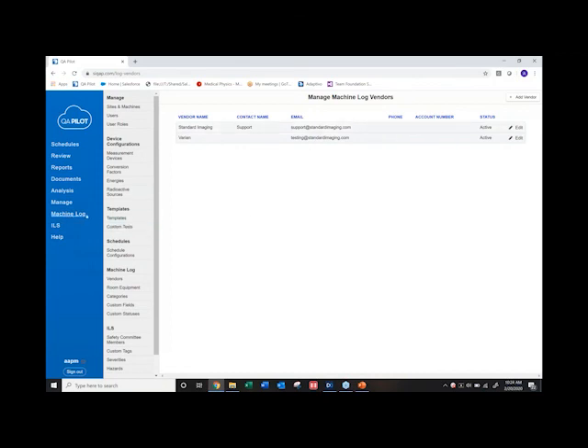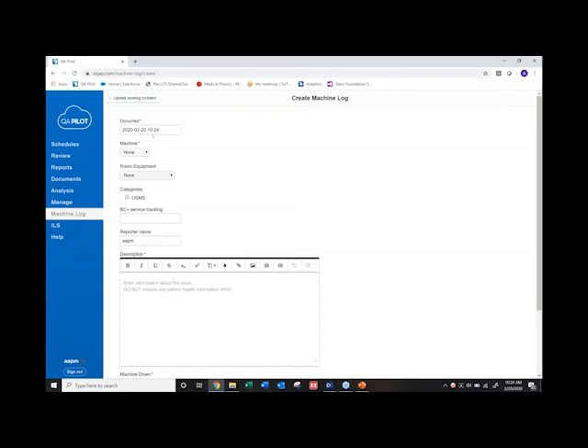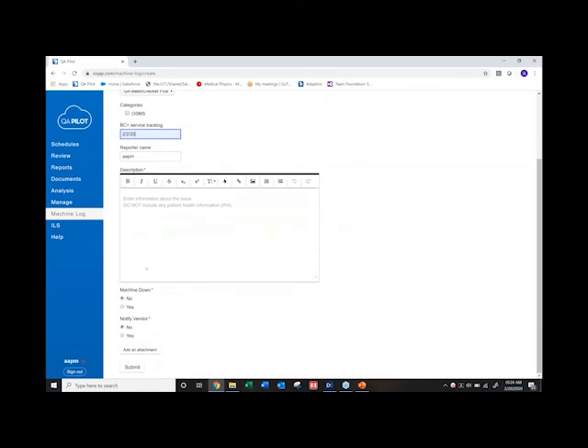And once you do that, if you go into machine log and you choose to log an event, now devices are tied to a Linac still, so we'll just say, okay, it's on the TrueBeam and it's our Beam Checker Plus. If we want to say service tracking, put in a date. I'll just use the one that's default there. Give your, who is it that's reporting the issue? Put in a full description. Machine, is it actually down or not down? Because maybe you get an error message, but you call into support and they solve that issue for you. But if it's determined in conversation with support that it needs to come in, you can go devices down.